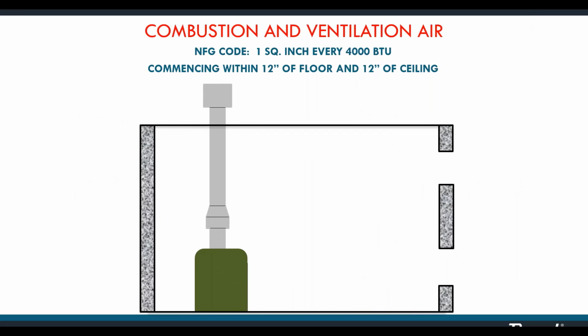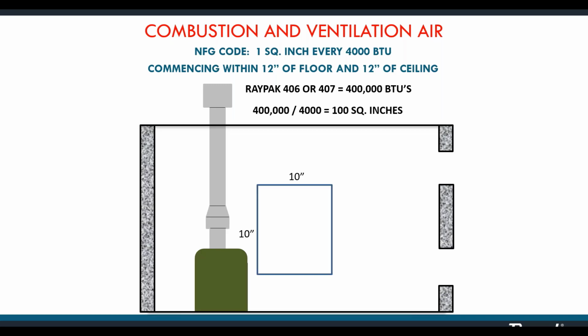So what they're saying is you need 1 square inch for every 4,000 BTUs, commencing within 12 inches of the floor and 12 inches of the ceiling. So 2 holes in the wall, 1 at the top, 1 at the bottom. As an example, if you've got a 407, 407 would be a low NOx product, so that's what we're talking about today. That's a 400,000 BTU product. 400,000 divided by 4,000 equals 100 square inches. That's a 10 by 10 hole, 1 at the top, 1 at the bottom.